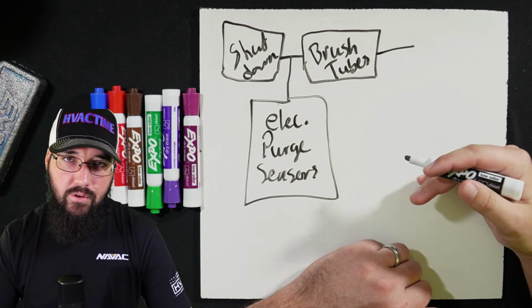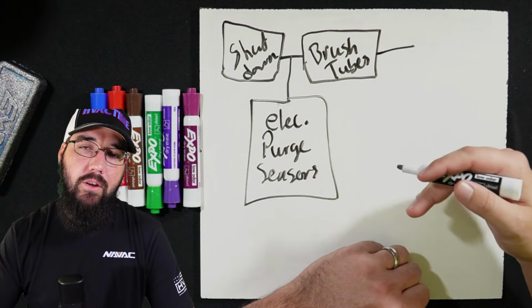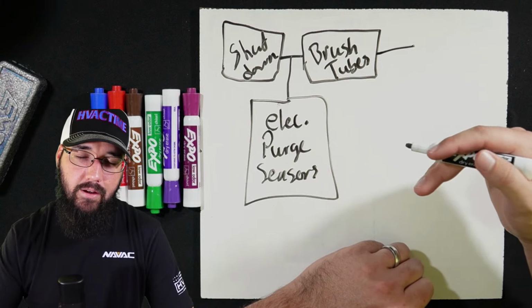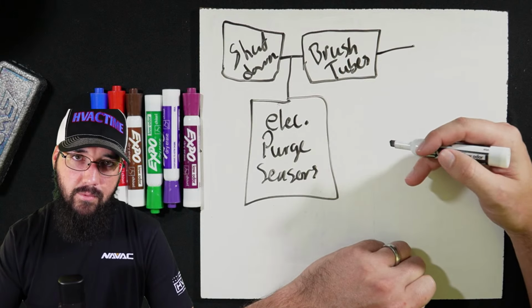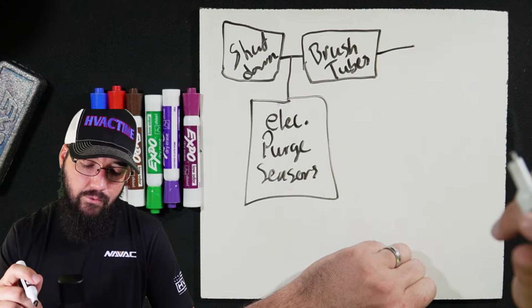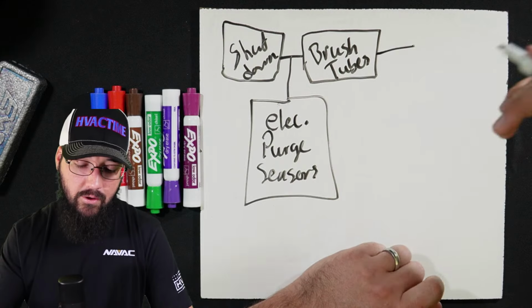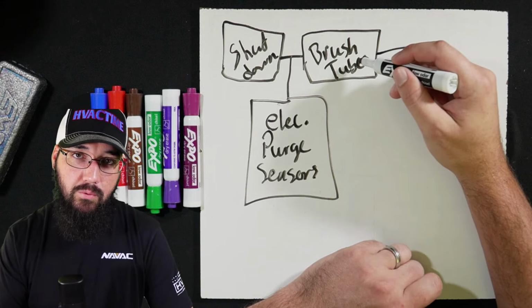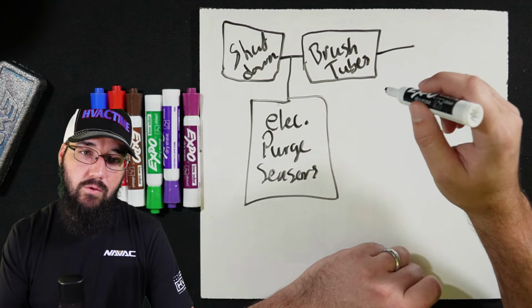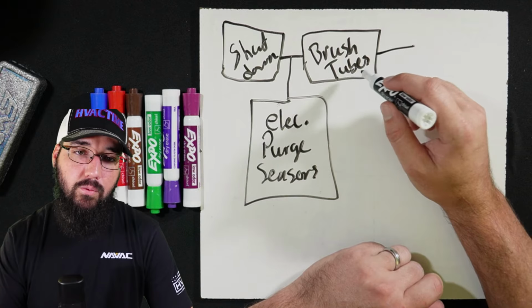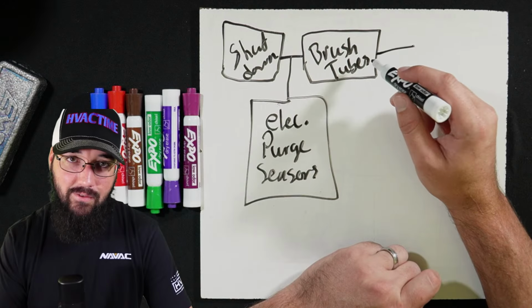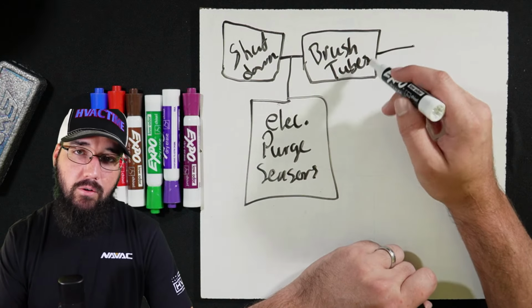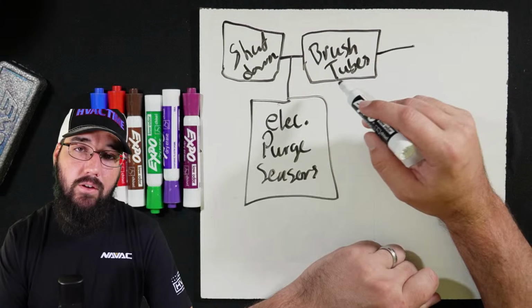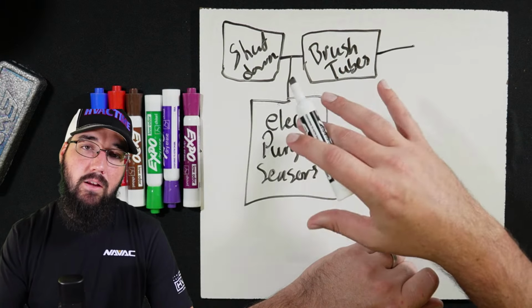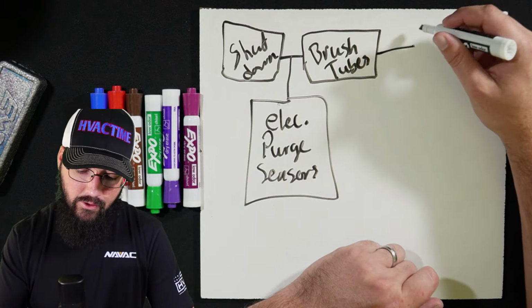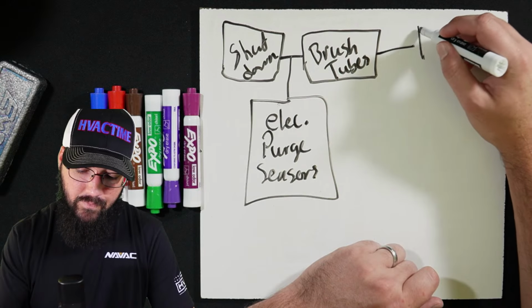Every 3 to 5 years, we should be opening the evaporator and checking eddy currents. Right? So if we're talking major as in we're going to eddy current, then this brushing tubes process will be more than just the condenser. This would get done on both condenser and evaporator. I'll usually start with the condenser, get it done, then do the evaporator.